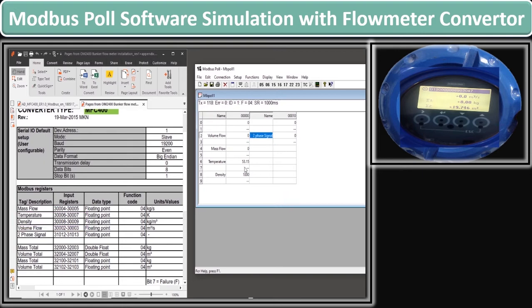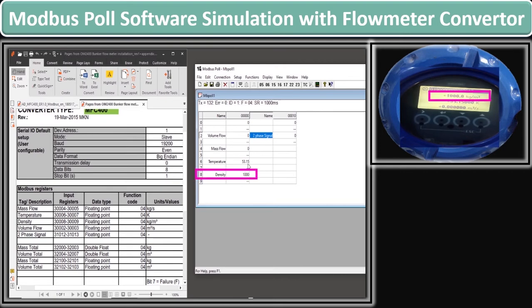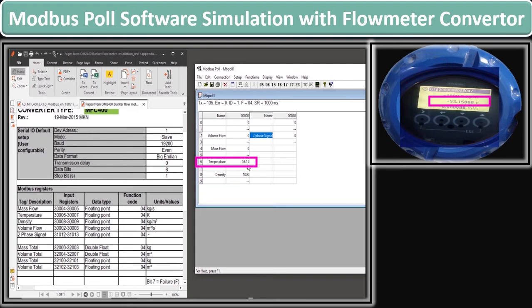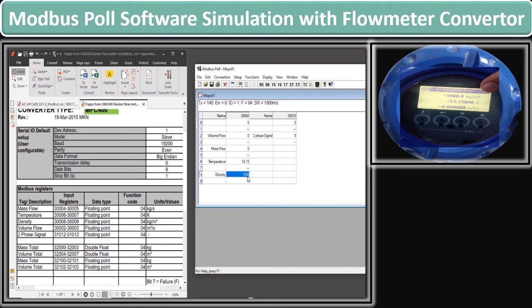Now we see these values on the flow meter screen as well. The flow meter is currently at the main screen. We will change the screen to see the values of temperature and density. You can see on the flow meter that the density value is 1000 kg/m³ and temperature is 53.15 K, which is also showing on our Modbus Poll software parameter values. Since the flow converter is not attached to a flow tube, we have to simulate the values of volume flow and mass flow on the flow meter and observe the result on Modbus Poll software.